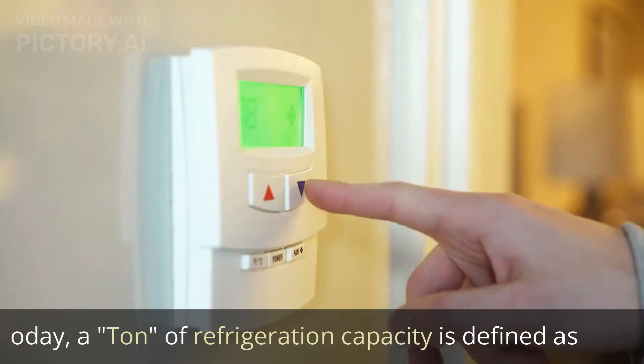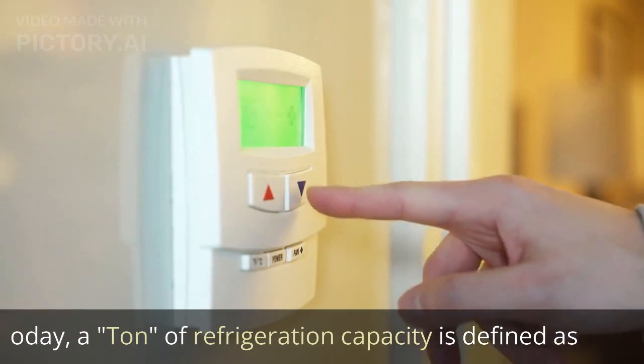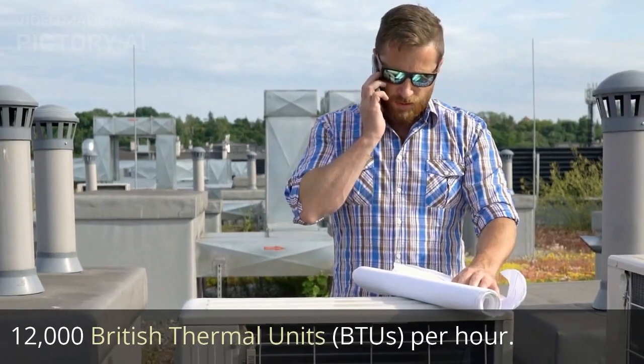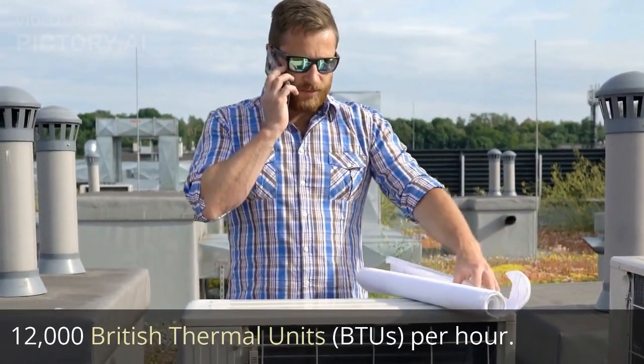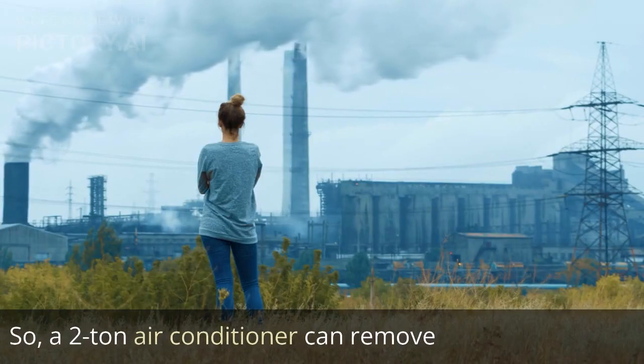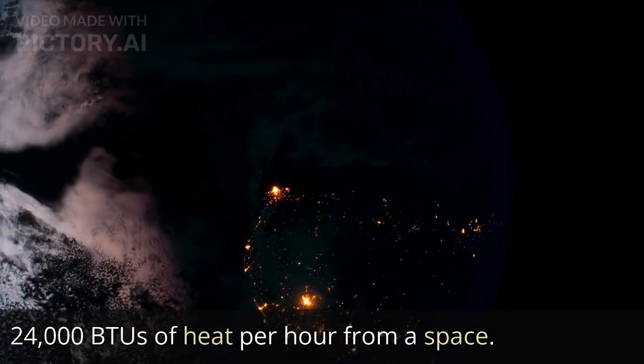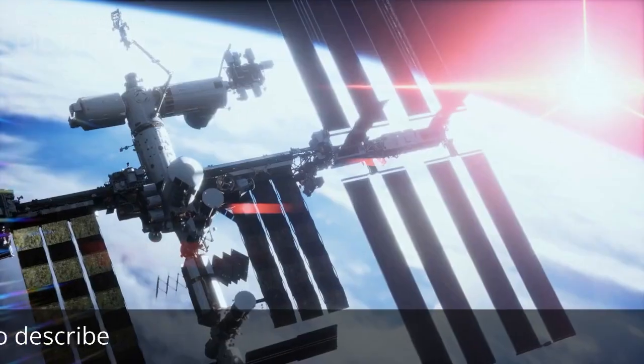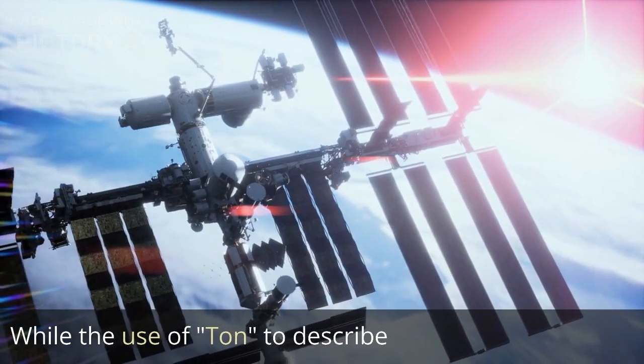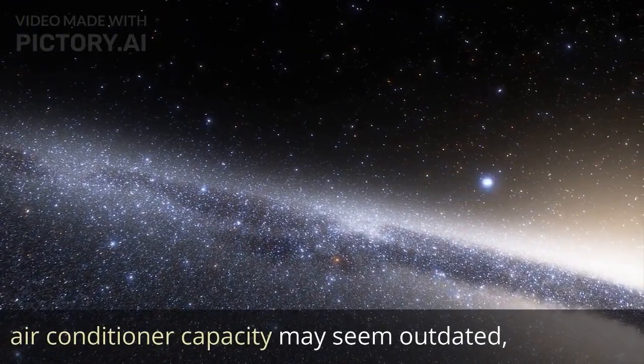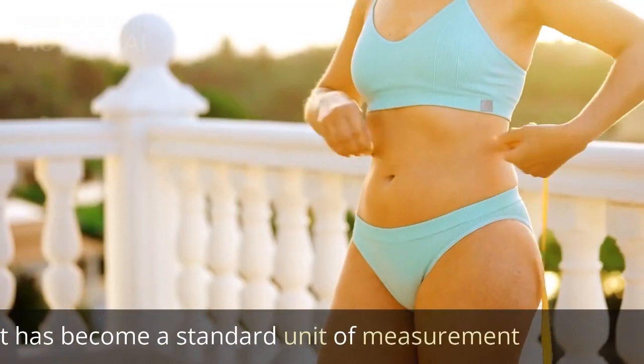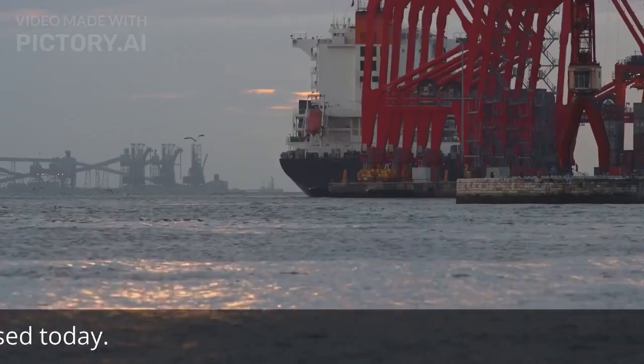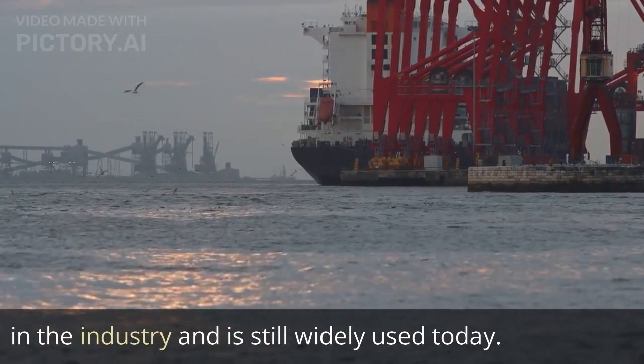Today, a ton of refrigeration capacity is defined as 12,000 British thermal units (BTUs) per hour. So, a 2-ton air conditioner can remove 24,000 BTUs of heat per hour from a space. While the use of ton to describe air conditioner capacity may seem outdated, it has become a standard unit of measurement in the industry and is still widely used today.